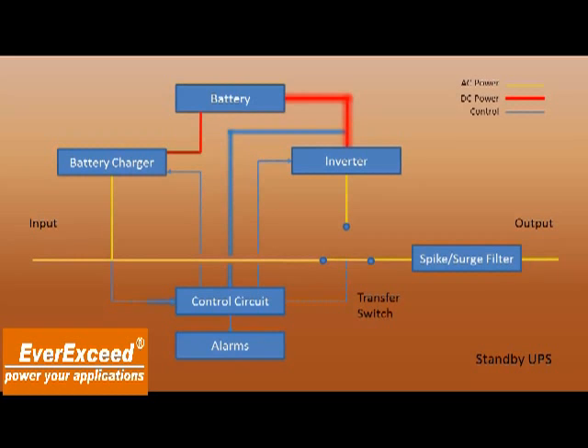When the power goes out to this unit, we'll see that we set an alarm and a number of things happen. Basically, the control circuit turns on the inverter, flips the transfer switch, and now we have an alarm set because there is no power on the input. Going back to our standby mode with a charged battery, we'll look at it one more time. The loss of power triggers alarm signals from the control circuit and the transfer switch. We have the power coming out.